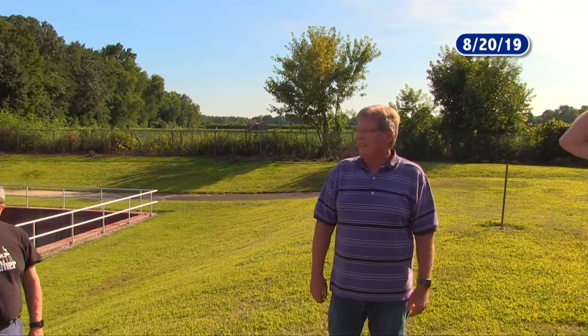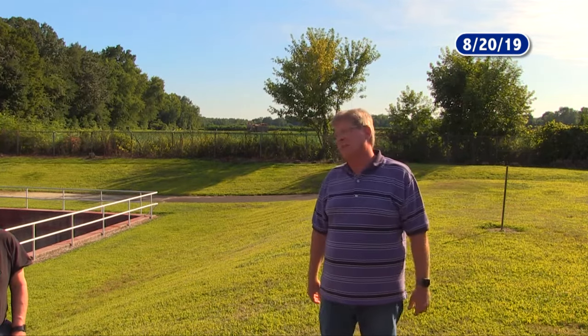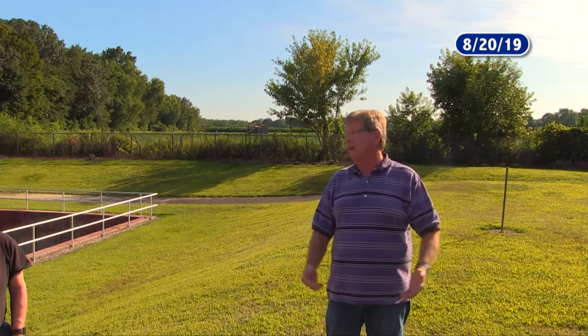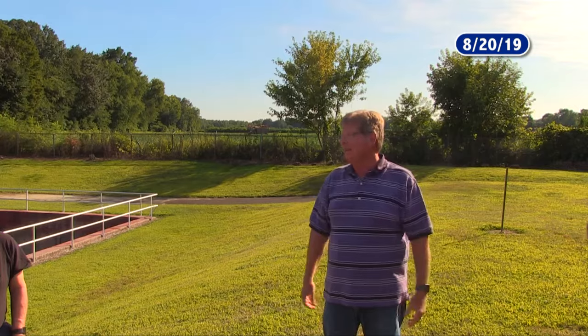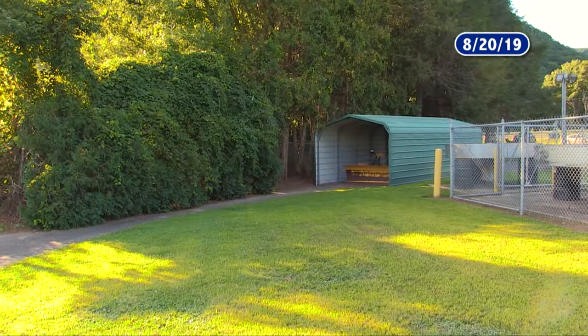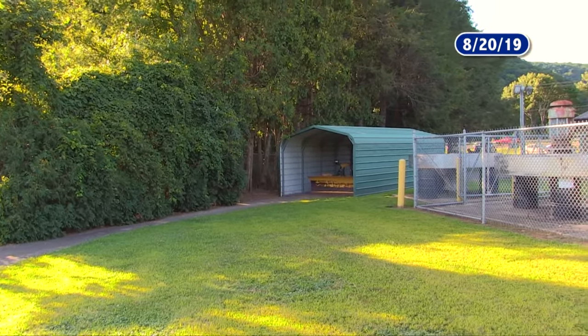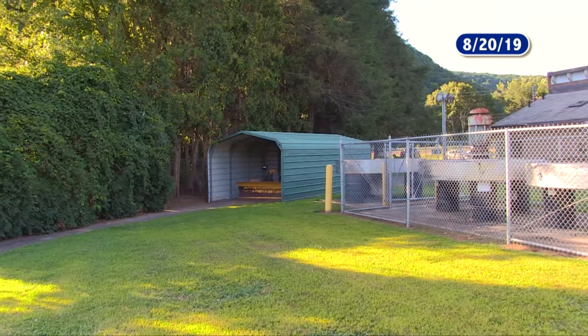Yeah. So when you talk about Headworks equipment, you're going to have to build another whole building. Yes. And have an operation inside. Well, you can get a Headworks that's out in the air, but in the Northeast, you're really asking for it if you do that. And now you're going to pay extra for a heater kit and then hope it works. So you're better off putting it in a little building that's heated. And where would that go? It would go right over here where that little carport is, right where that car is, right in there generally. A small building would house all of it.